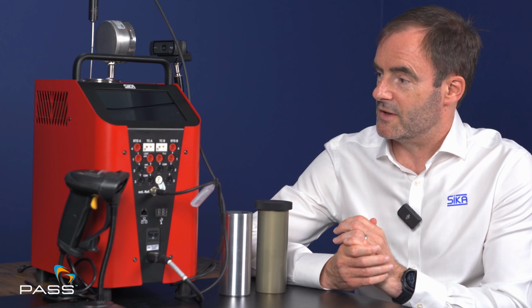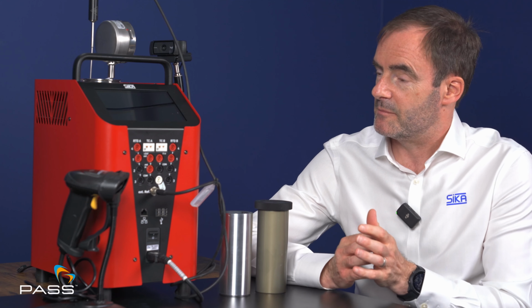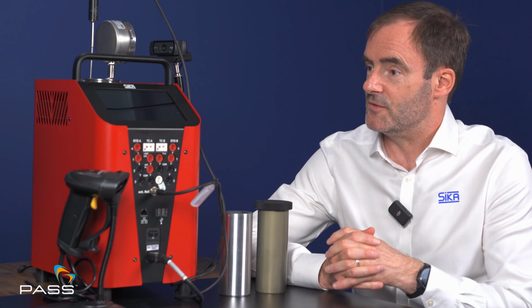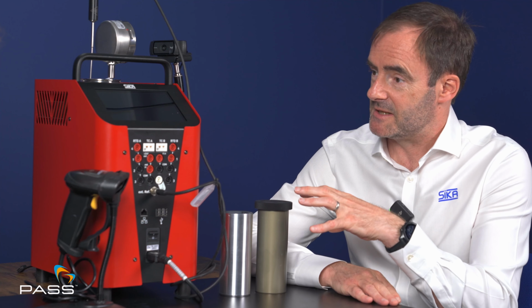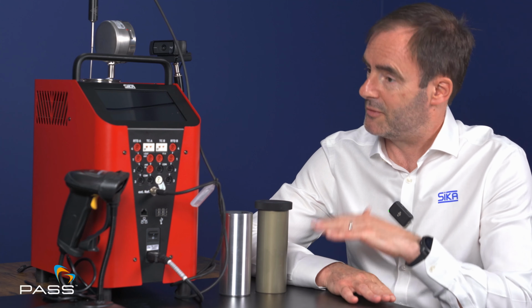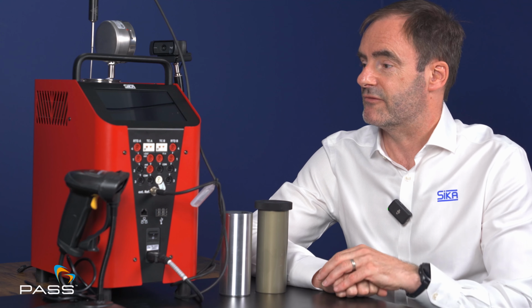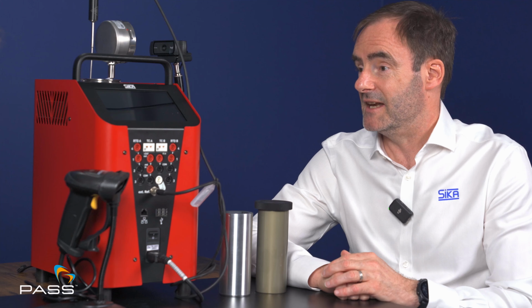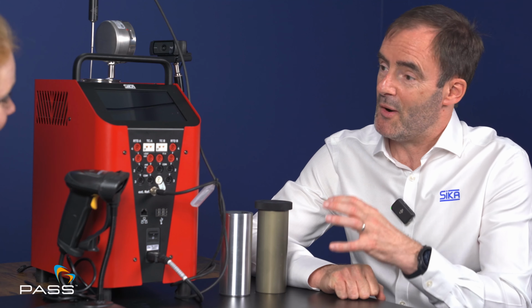Okay. So could you tell us about the Rocket Controller and why it's so revolutionary? Yes. This is a patented design from Sika. The Rocket Controller is named because part of the algorithm that is used as part of the stability process we have when we're ramping up or reducing the temperature is taken from the Apollo rocket landing algorithms. So that's only part of that. But we use that to arrive at the stability temperature range that customers need before they can actually take a reading and then move on to the next temperature point.